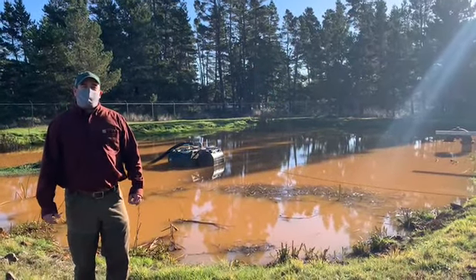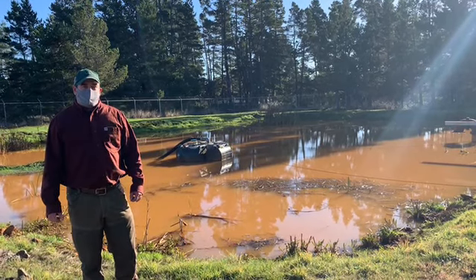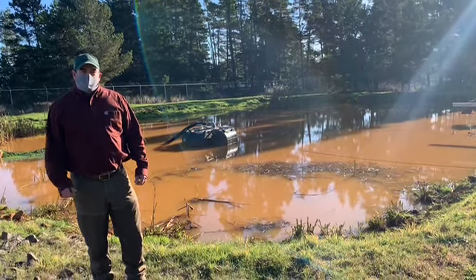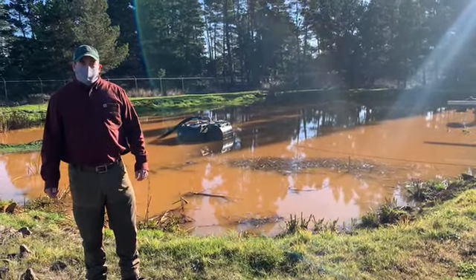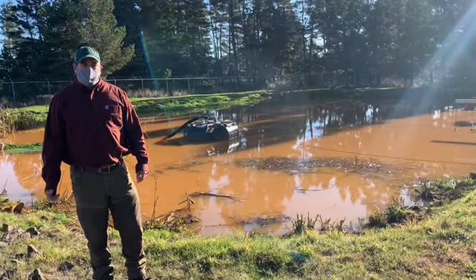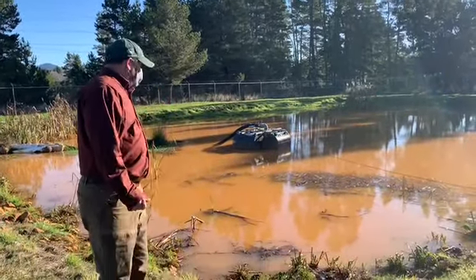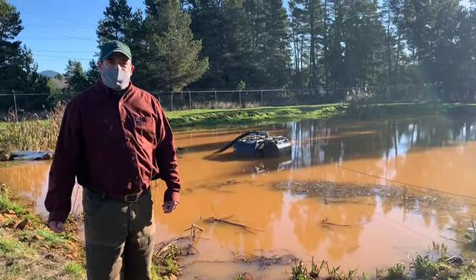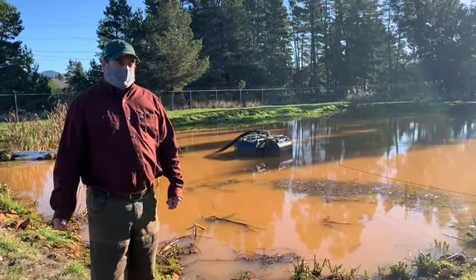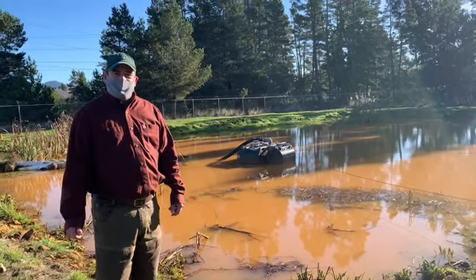One of the processes of treating water is cleaning the filters. Over time the filters clog up with dissolved iron accumulated from inside the aquifer, and we backwash the filters. That backwash water is sent to our lagoons out here at the well field, where the dissolved iron can settle out on the bottom so that only the clean water is filtered back into the aquifer. As you can see, the water is quite discolored — that is the iron separating inside the backwash water. This is also very good habitat for frogs. So we're cleaning water for the City of Florence and also providing habitat for wildlife.